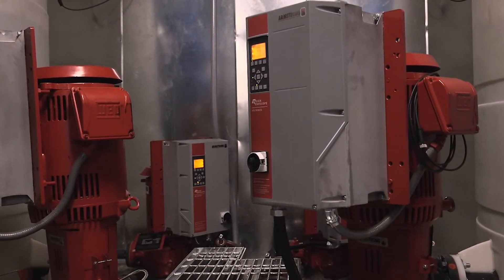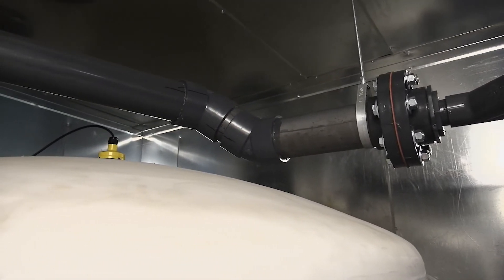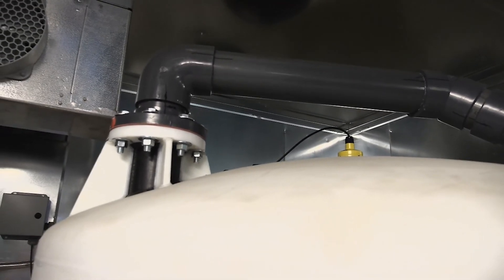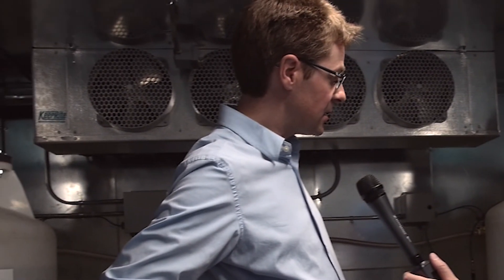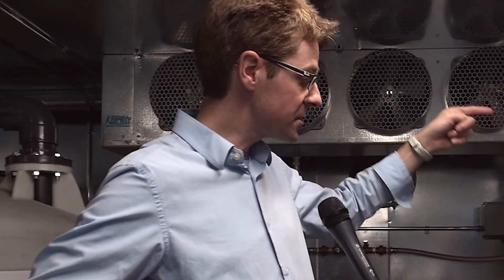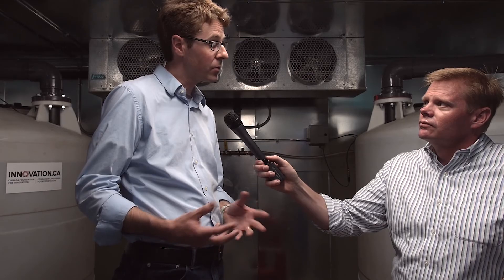How do you assess or harvest the biofilm once it's accumulated inside the pipe? It's actually grown in a native way — we just use local water to grow the biofilm inside the pipe wall, and that usually takes about 60 to 90 days. We have removable coupons that we can take from the pipe and look at the microbiological composition of the biofilm using a microscope or DNA sequencing analysis, to see what bacteria, protozoa, and fungi actually reside on the wall.